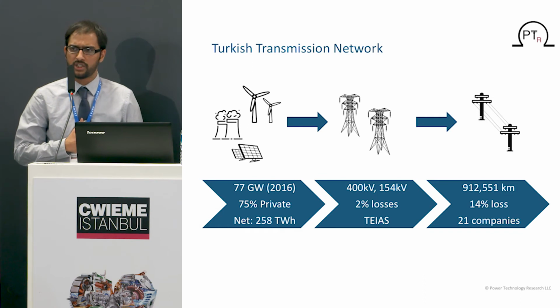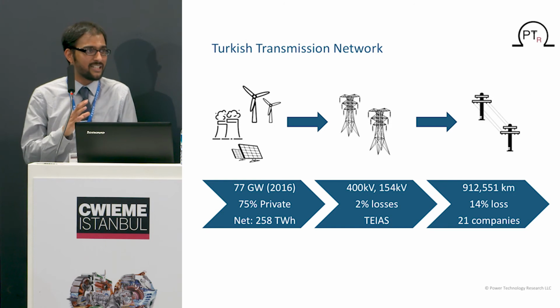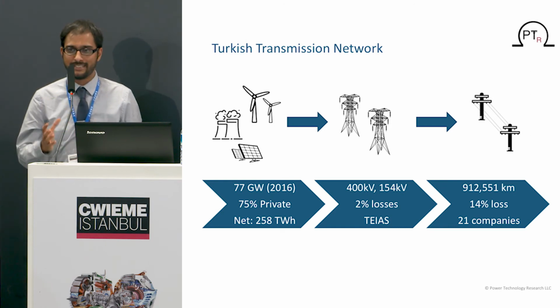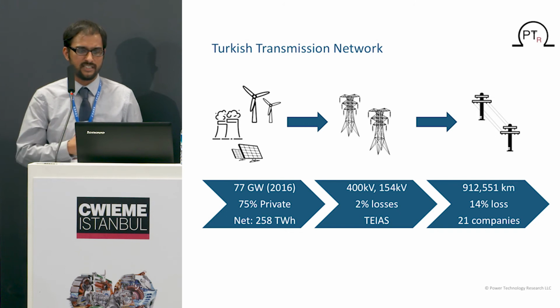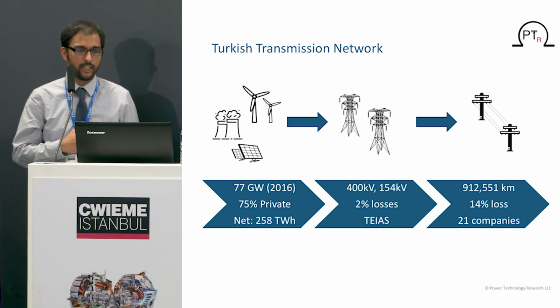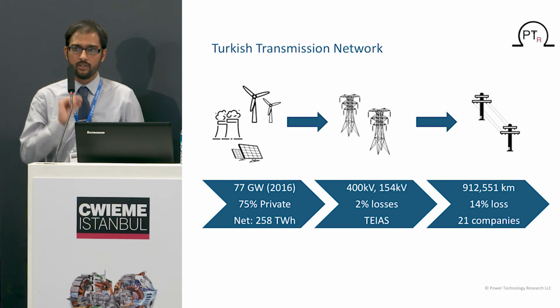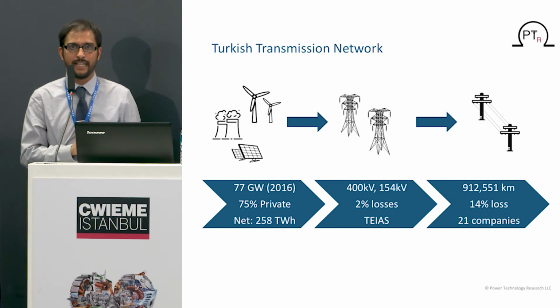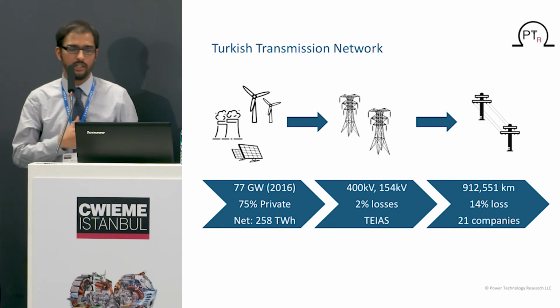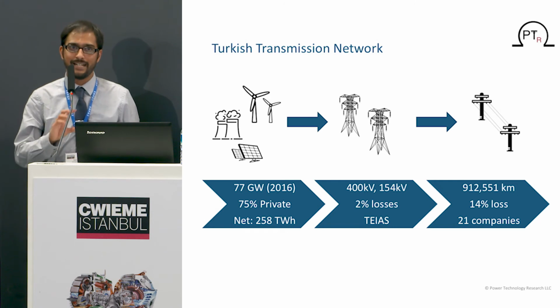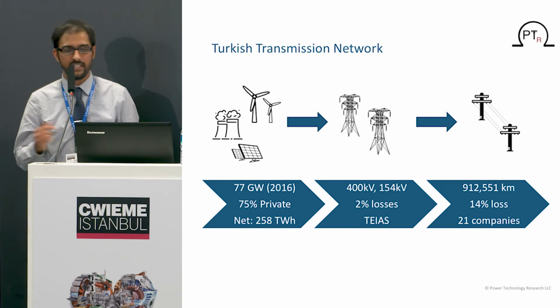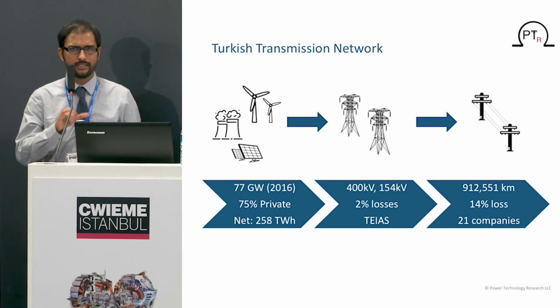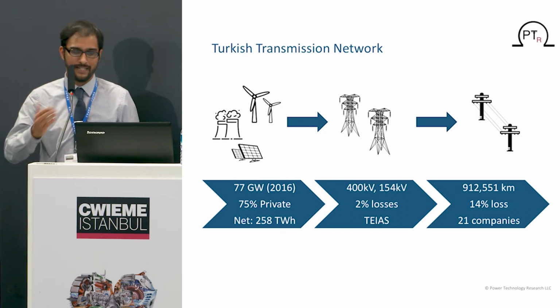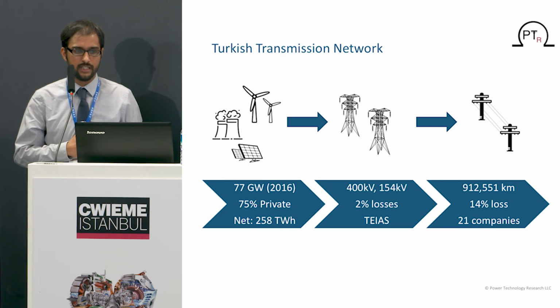First, a brief introduction to the T&D and generation infrastructure of the Turkish market: 77 gigawatts was the generation number in 2016, roughly 75% privately owned and 25% publicly owned. Investments are going into two voltages, 400 kV and 154 kV. Even though 66 kV is within the transmission network, it's getting replaced by the 33 kV network. Losses are on the lower end for transmission but higher for distribution within Turkey's network.